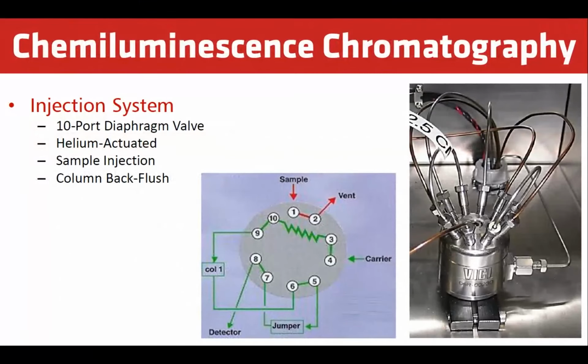So the chemiluminescence chromatography, it uses an injection system, a 10-port diaphragm valve, helium-activated sample injection, column back flush. On the right is just a typical 10-port valve that we use, and you can see the flow pattern on the valve. So basically, you got a sample come in, sample vent, carrier comes in on port 4, picks up the sample, takes it to the column, to the detector, and then once you get the sulfurs of interest out, you simply backflush the rest of the sulfurs out as other sulfur.